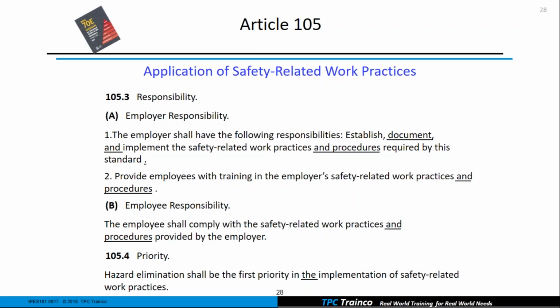Next, we're getting out of definitions now, and we get up into Article 105, and employer responsibility. Just about everything falls on the employer, whether it's OSHA's Code of Federal Regulations, 1910 and 1926, or NFPA 70E. The employer shall have the following responsibilities: establish, document, and implement the safety-related work practices and procedures required by this standard. So you have to have an electrical safety program, and it has to be documented, and you have to use it. Also, you have to provide employees with training in the employer's safety-related work practices and procedures. That training also should be documented. But you have to have that training down.